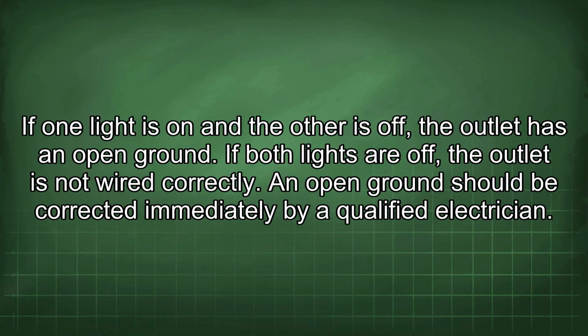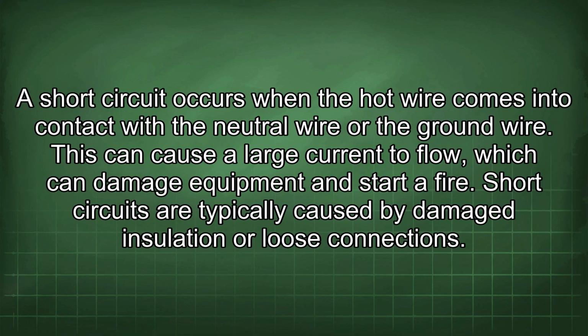If one light is on and the other is off, the outlet has an open ground. If both lights are off, the outlet is not wired correctly. An open ground should be corrected immediately by a qualified electrician. A short circuit occurs when the hot wire comes into contact with the neutral wire or the ground wire. This can cause a large current to flow, which can damage equipment and start a fire.